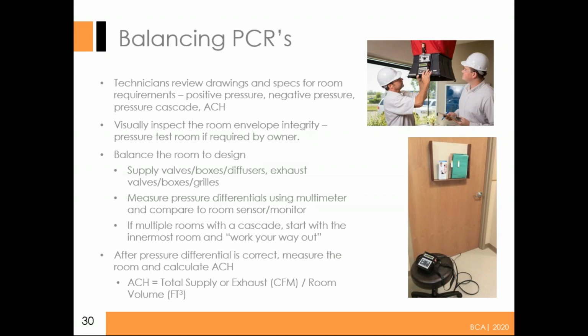Let's say you're not making that differential pressure. So the integrity plays a role in that, door sweeps and so forth. So you can have a little play in your exhaust to vary from the design criteria as far as the design numbers to achieve that. A lot of the things we find is like the pressure monitors not being in calibration. Verifying that, once again, Kurt, you know that very, very well, talking about how to make sure you're zeroed out and so forth, and taking your differential pressures after you get the room set up. I'm trying to not get too crazy, but be a little bit more specific on test and balance.